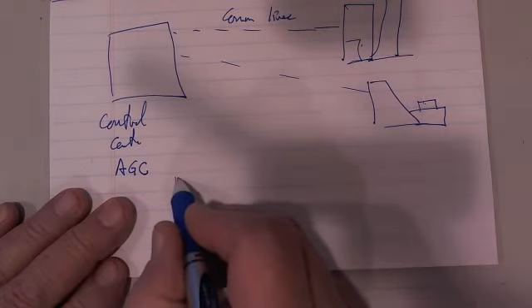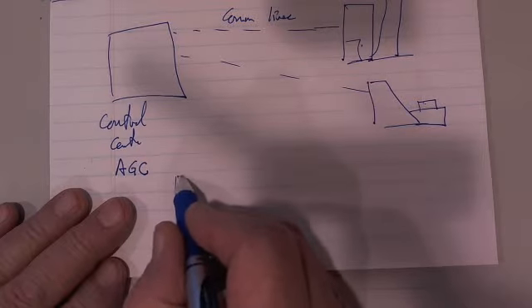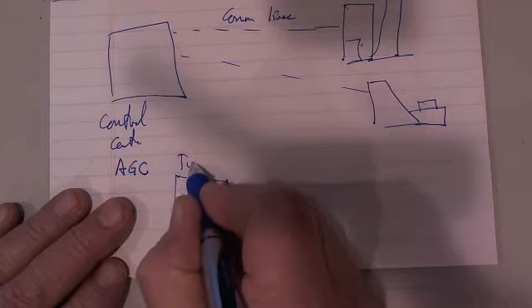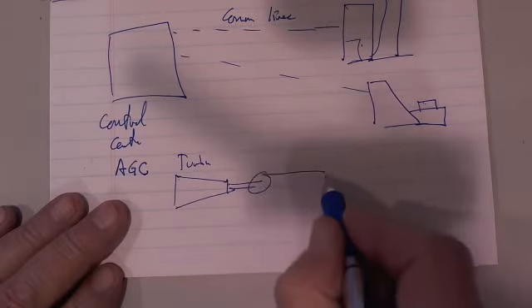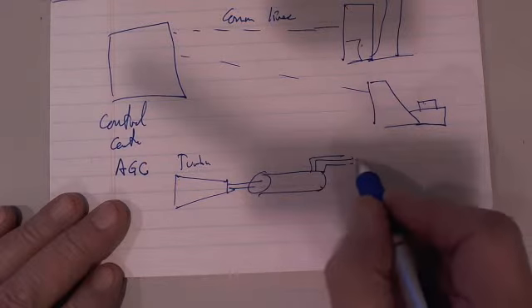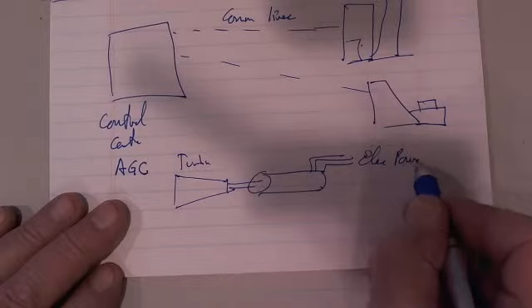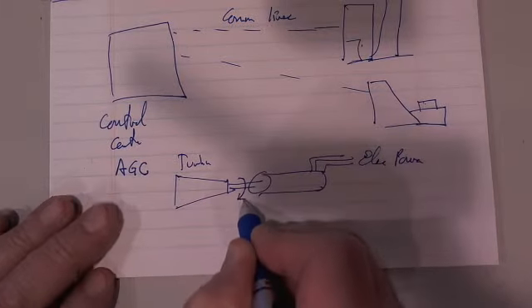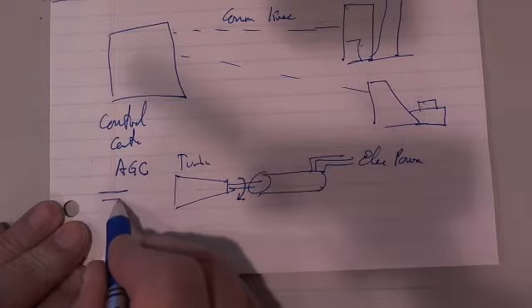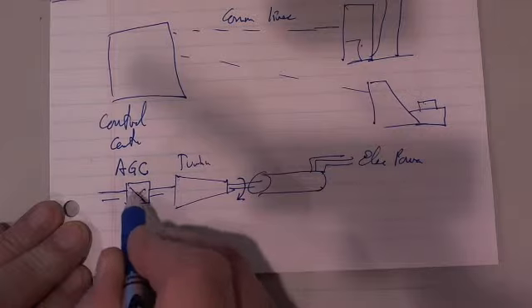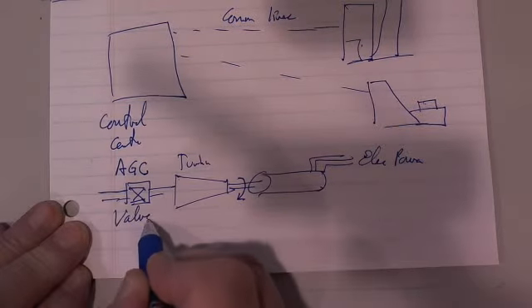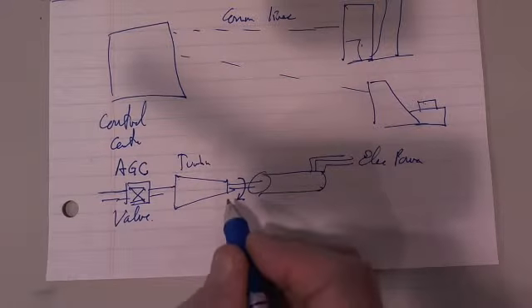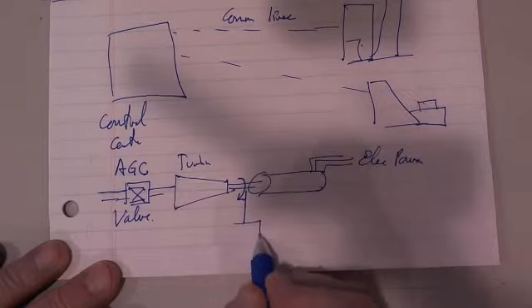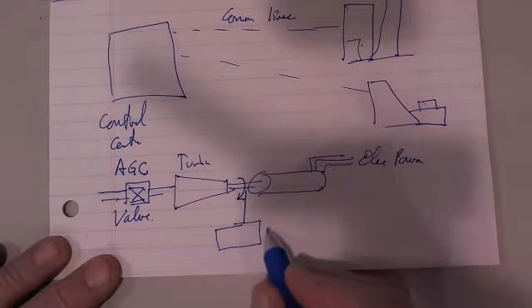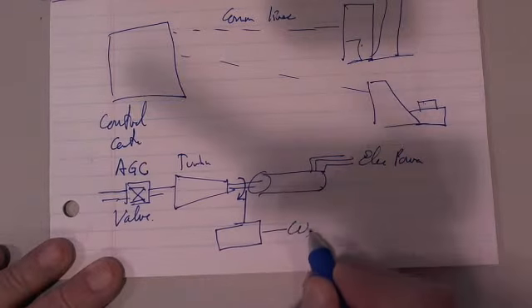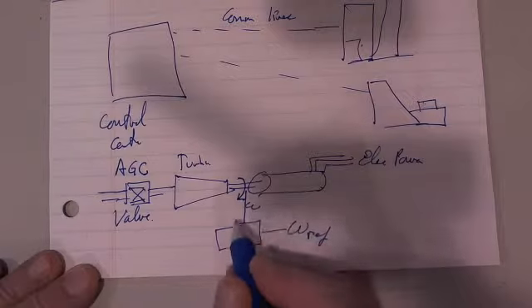We have a steam generator here. Here's a turbine. Here's a shaft. Here's a generator. Here we have the electrical output. But the shaft is rotating. Okay, it is rotating, and here's the steam coming in, and there's a valve. So just draw. Here's a valve, and we're going to show you various drawings later. But we measure the rotational speed. We measure the rotational speed, and we have an omega reference. Here's omega, the speed of the shaft.